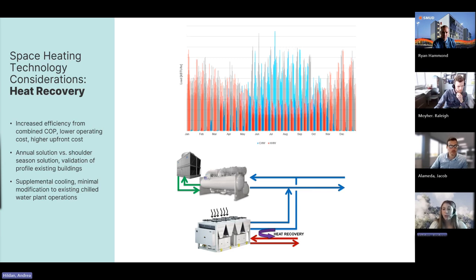So I think it's really helpful when we're evaluating heat recovery on existing buildings with already limited space for new equipment. In this example I have here on the screen, another great aspect of this system is that it's interfacing with existing chilled water plants with minimal invasiveness on how that system is operating on its own, and you're able to interconnect systems that have traditionally been independent.